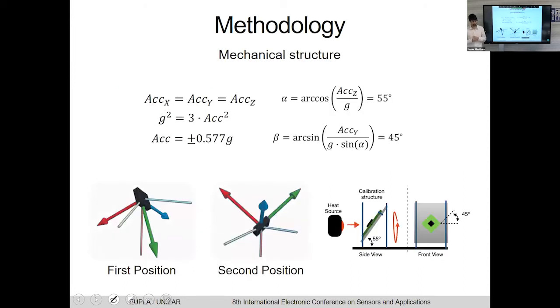As we only need two positions, we are going to get the broadest range in all the three axes, and this is achieved with an acceleration of 577 milligees in each axis. This corresponds to a pitch angle of 55 degrees and a roll angle of 45 degrees. These are the two resultant positions, and we propose a simple calibration structure that is a plane that allows the user to quickly alternate between the two positions during the test.